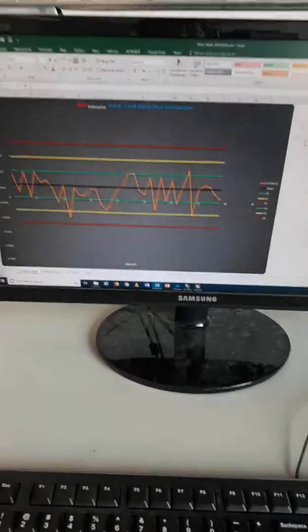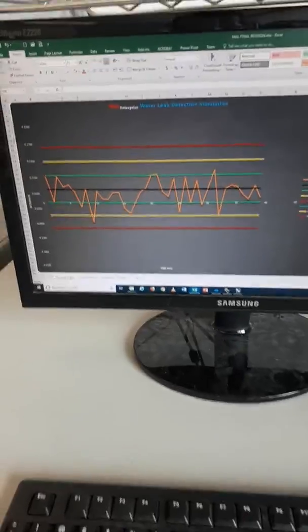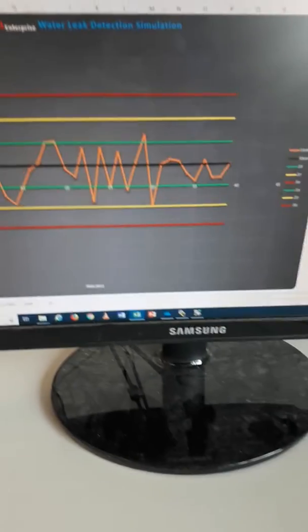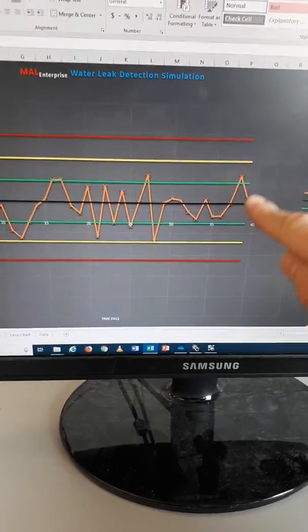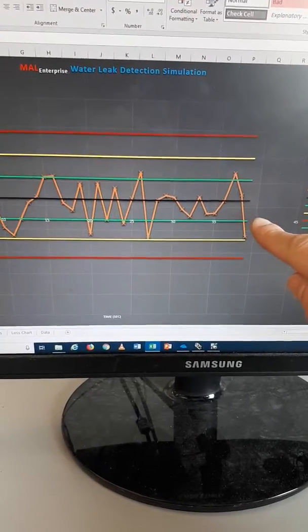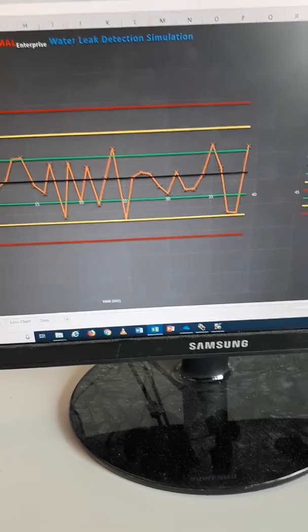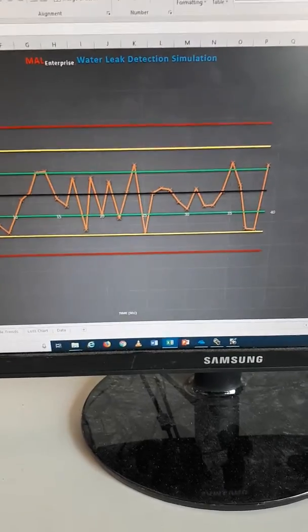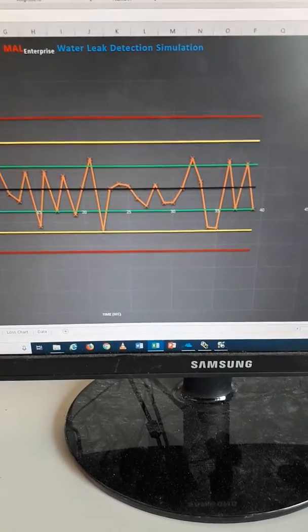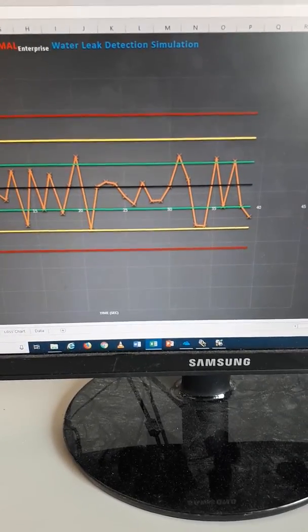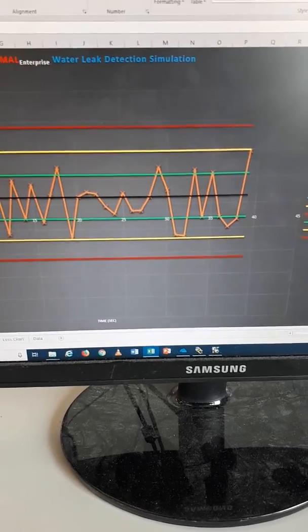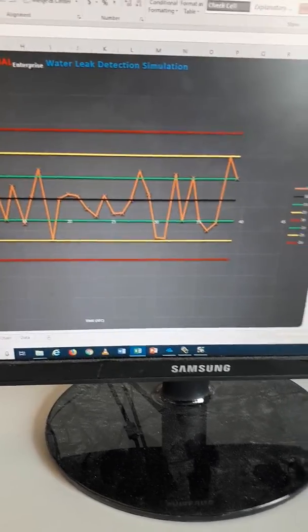Over here, we have our control charts. This is where we're applying statistical process control to our system. This is the variance between our supply and our usage in the system. As you can see, it's following the control chart as it's supposed to, following within the upper and lower control limits, most signals being within one sigma of standard deviation.